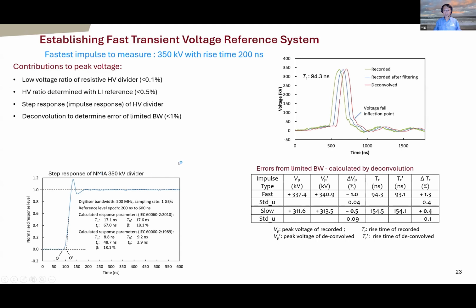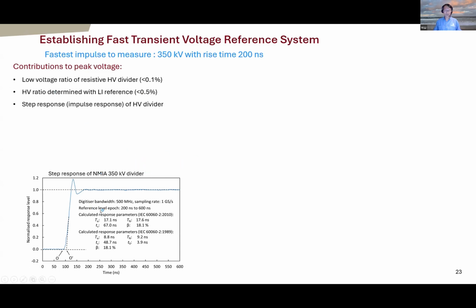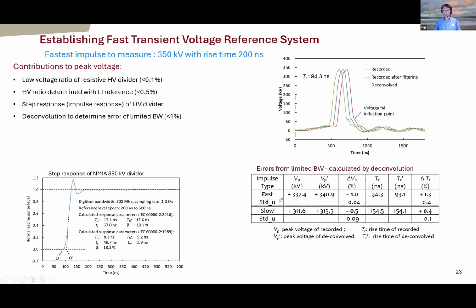Another example is the fast transient. Again, you measure the step response, and in here you do the deconvolution of the recorded waveform and the waveform calculated by the deconvolution. You can see for the fast pulse with 94 nanoseconds rise time, you achieve about 1% difference. For a slower pulse, it's 0.5%. So for this very fast pulse, we can also confidently measure within a couple of percent.